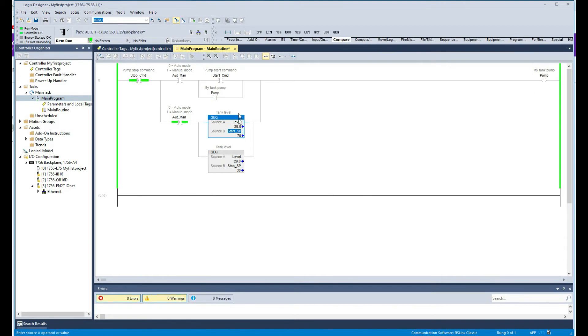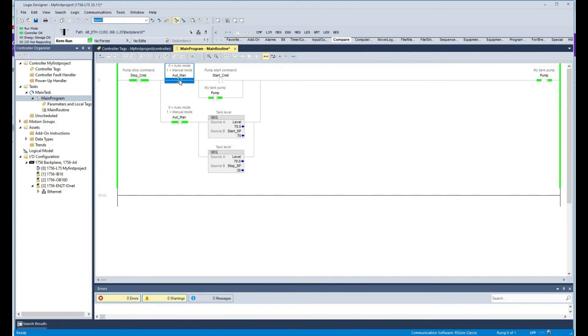In auto mode the pump waits until the level is at 70 or above to start automatically. If I switch to manual mode while the pump is running, the pump stays running — that's a bumpless transfer between manual mode and auto mode. That's how this logic works.